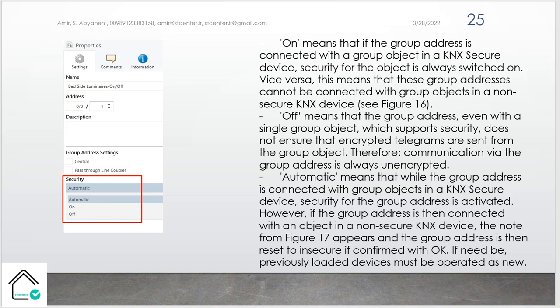If you put it in automatic, and I think by default it is automatic, it means that while the group address is connected with a group object in a KNX Secure device, security for the group address is activated. However, if the group address is then connected via an object in a non-secure device, a note appears, and the group address is reset to insecure if you confirm it. So if you put it in automatic and you link the secure group object to this group address, it is secure. If you then add more objects that are non-secure, the group address is automatically turned to non-secure. Of course, there is a warning pop-up, and you should confirm it.